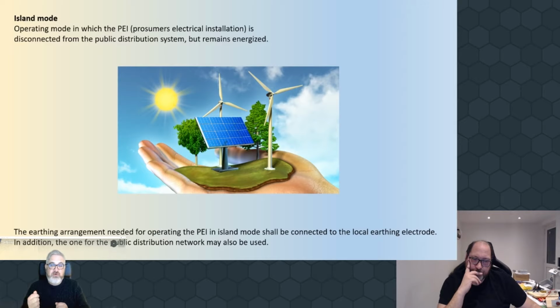In addition, the one for the public distribution network may also be used. So the way I've seen this, and there are drawings that show different configurations, is yes, you will be connected to your DNO, but at any one point you may be able to switch that out and use your own local earth electrode network as a local earth reference.